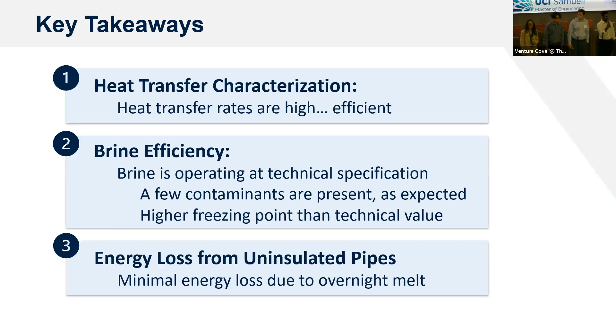We also tested for the freezing point of the brine, and we noticed that the freezing point was significantly higher than what the manufacturer stated on the data sheet. Last but not least, the energy loss from uninsulated pipes: we realized that the energy loss is so insignificant, or too low, that it doesn't affect the overall cooling system much.